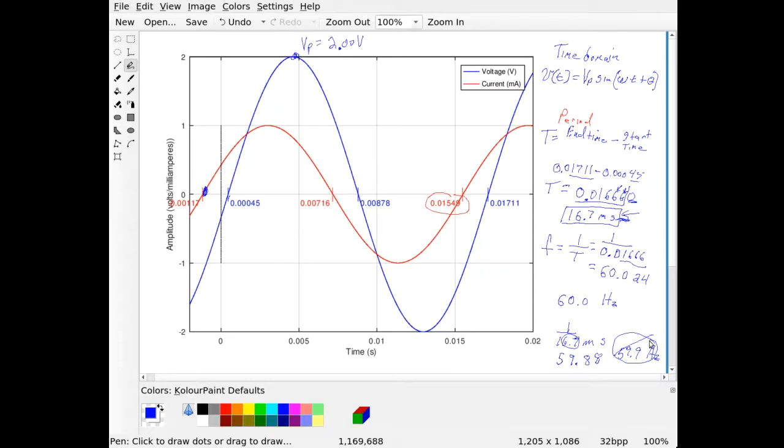And by the way, the electric company never lets the frequency get off by 0.1 hertz. That's a huge error for the electric company. The electric company monitors that frequency of 60 hertz, and if it gets to 59.9 hertz, that's considered very, very bad for them.